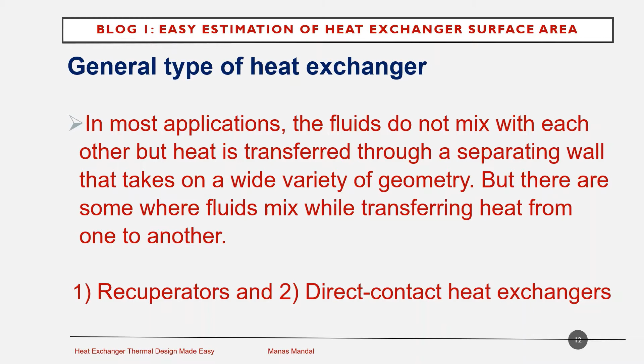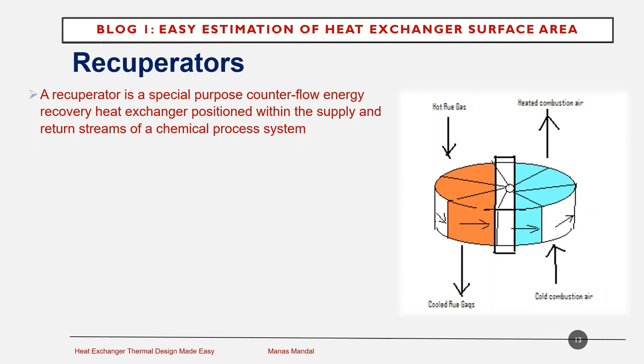A recuperator is a special purpose counterflow energy recovery heat exchanger positioned within the supply and return streams of a chemical process system. It can be an air preheater also in a furnace, where exhaust and flue gases exchange heat with combustion air, which is cold, in order to recover the waste heat from the flue gases.